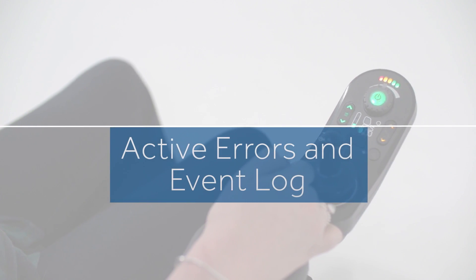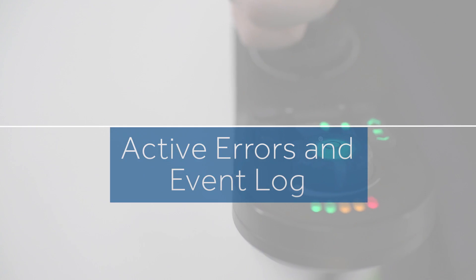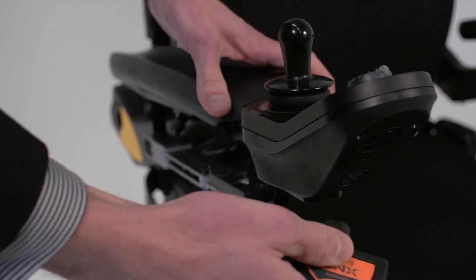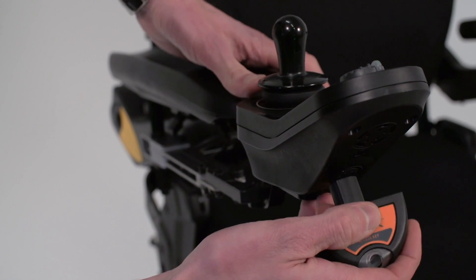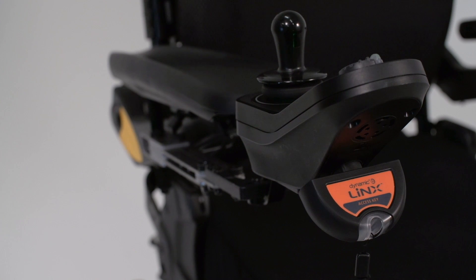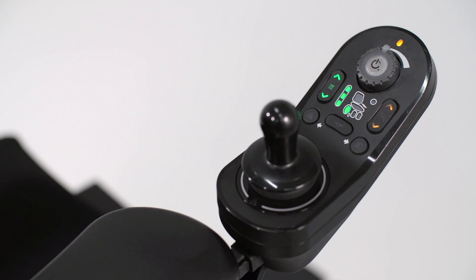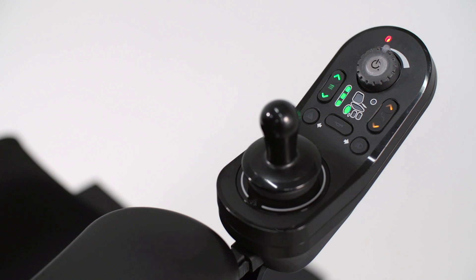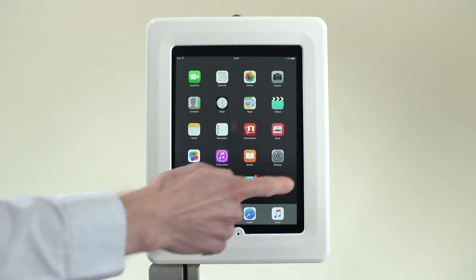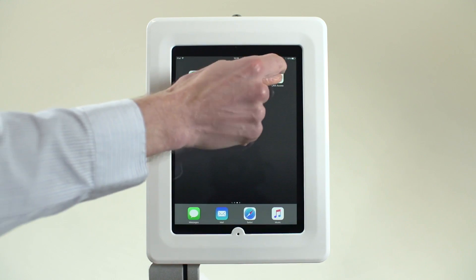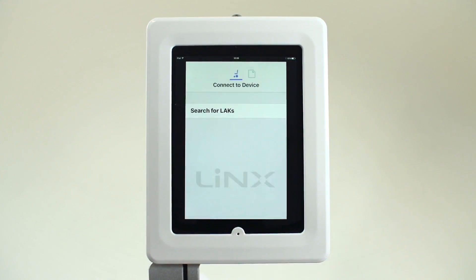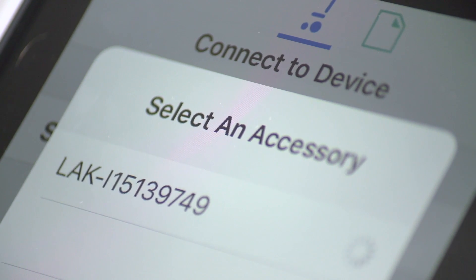Active Errors and Event Log. Lynx allows active errors present on the power chair to be easily identified. If a flash code is present on the Lynx control system, the status light will flash red. The flash code can be identified by counting the number of flashes, or alternatively can be accessed via the active error menu within the Lynx iOS app.